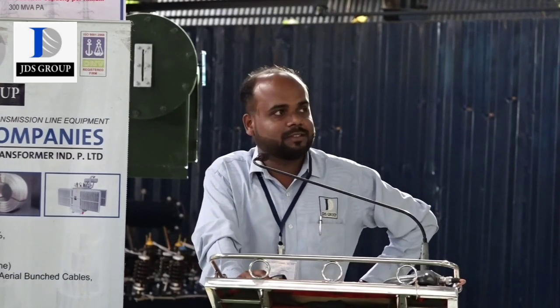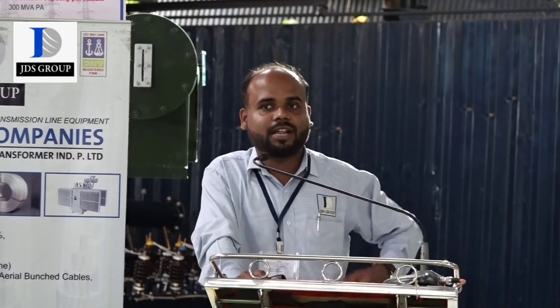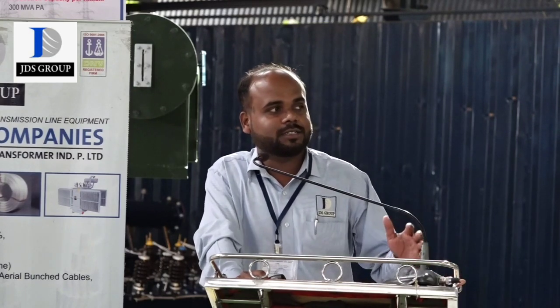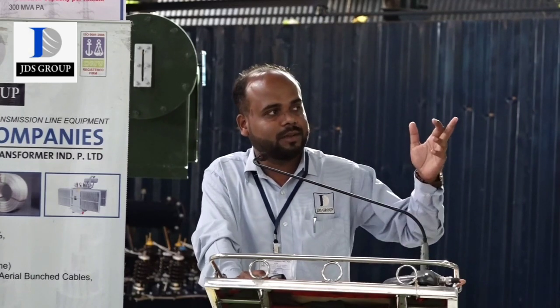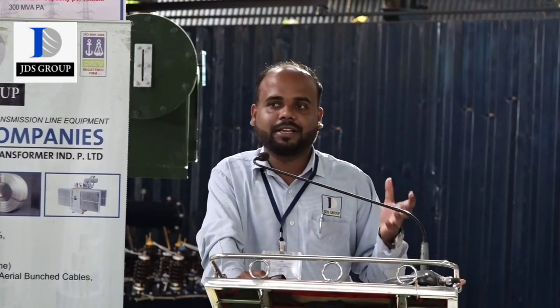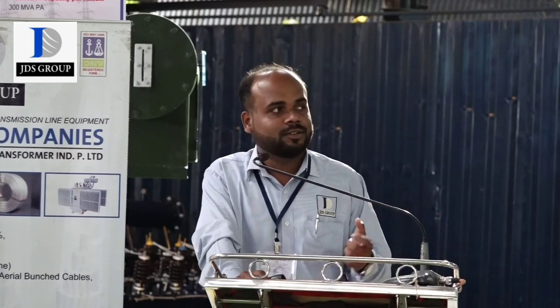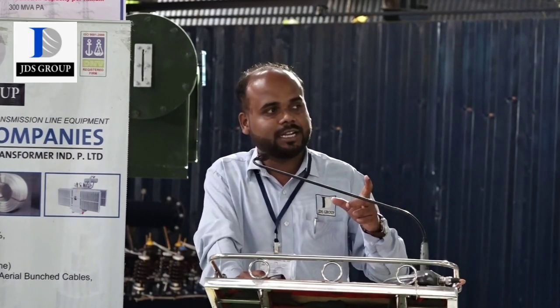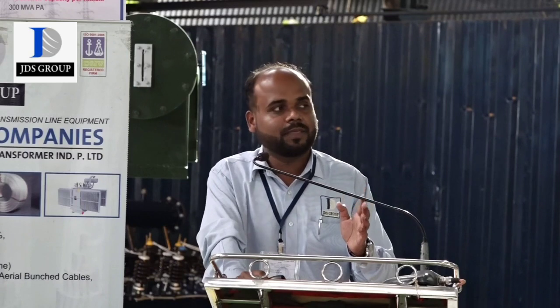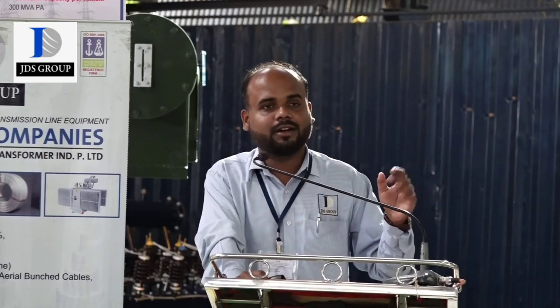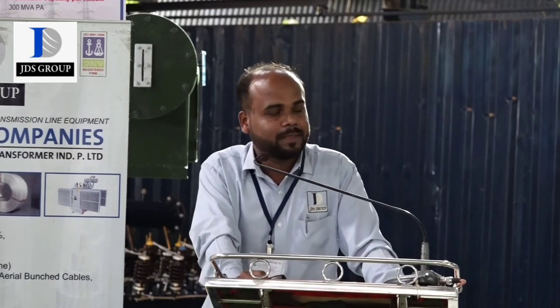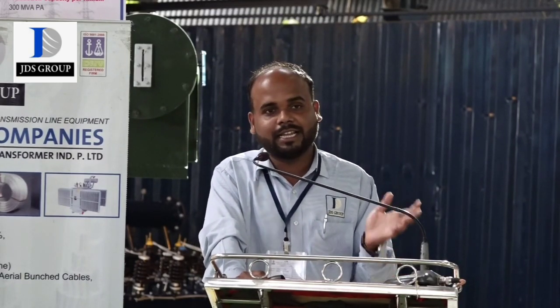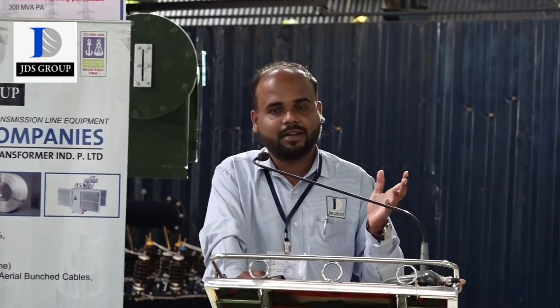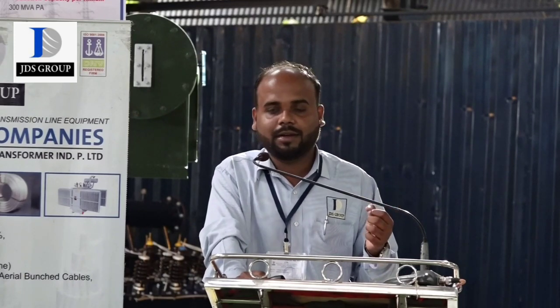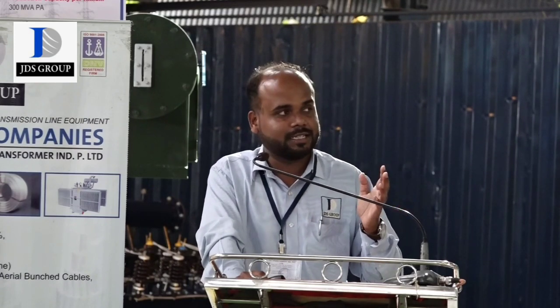Another thing that I will tell about the transformer is the protection of the transformer. If a fault occurs in the transformer, what are the different things that are there? For example, the oil temperature indicator. If the temperature of the oil increases, how will we know? So an oil temperature indicator has been provided, and a winding temperature indicator has been provided. It has been set to some value. Whenever the temperature increases beyond this value, our control panel connected to the OLTC, if you visit the site, the control panel has been connected. If the transformer oil or winding temperature suddenly increases, the alarm in our control panel starts. So by this we come to know that the oil temperature or winding temperature has increased.